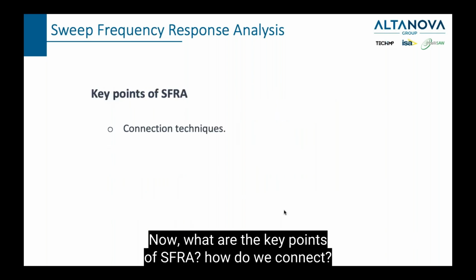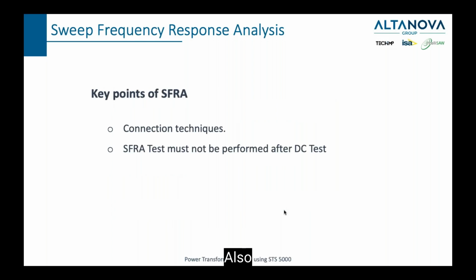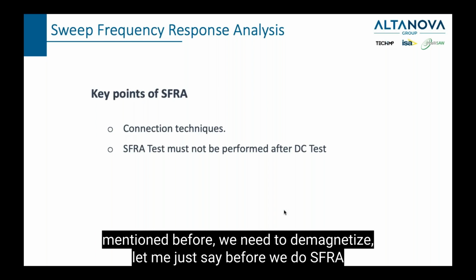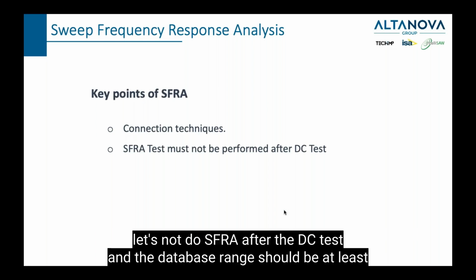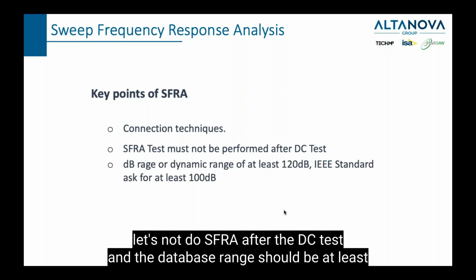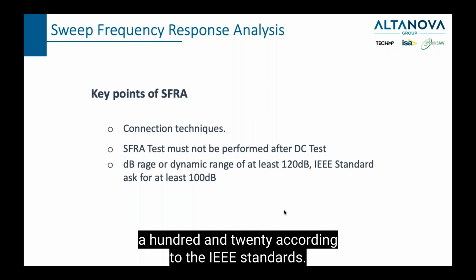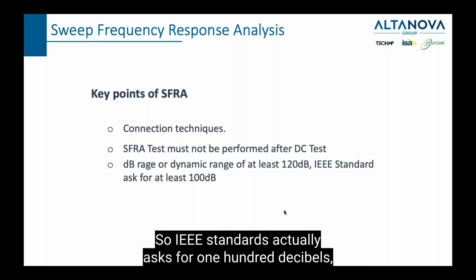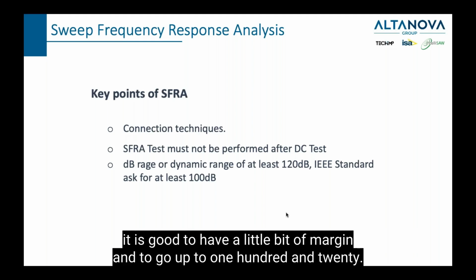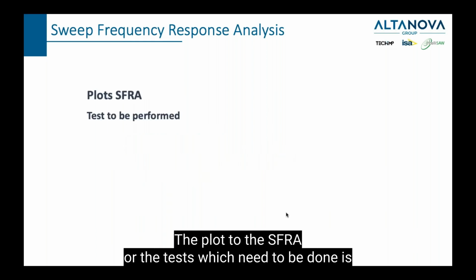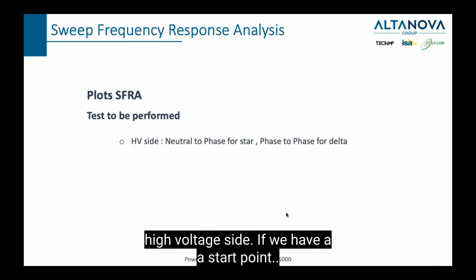Now, the key points of SFRA are how we connect. Also, as mentioned before, we need to demagnetize, or let me just say, let's not do SFRA after the DC test. And the dB range should be at least 120 according to the IEEE standards. So the IEEE standard actually asks for 100 decibels, but to be sure, it is good to have a little bit of margin and to go up to 120. The plots for the SFRA, or the tests which need to be done, is the high voltage side.